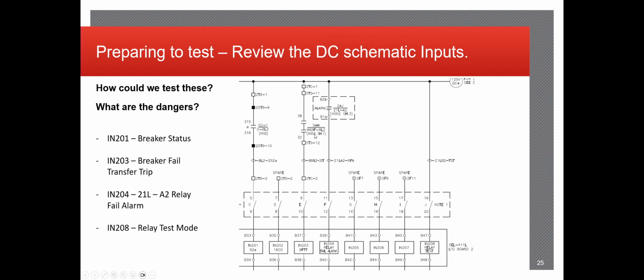Like we said, the breaker failure. In this case, it's a breaker failure transfer trip. So this lockout operates and sends a signal. The transfer trip may also send a signal to another relay, maybe in this control house or possibly another control house over the fiber lines. So again, understand that everything that may occur when operating this contact is completely isolated and within the boundaries of the scope of work, and then everything will be all set.